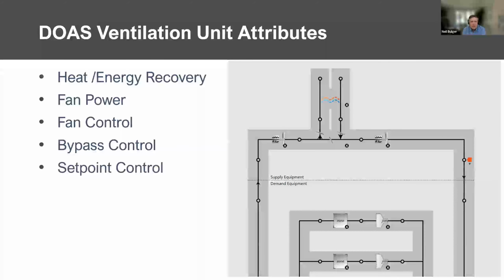And lastly, I have one slide. So the DOAS unit, if you do have ducted outside air, does it have heat recovery? Again, how is the fan powered? Is it controlled? A lot of these systems, even in multifamily, right, you might have balanced ventilation with an HRV or an ERV. It might just be on at constant volume quite often. You can definitely get more detailed into these. You could add zone control, DCV controls, but trying to think, what can we do in the design and what can we represent in the model? There's a lot of other trainings I've done on DOAS controls, and I link to some in the end, but critical to efficiency.